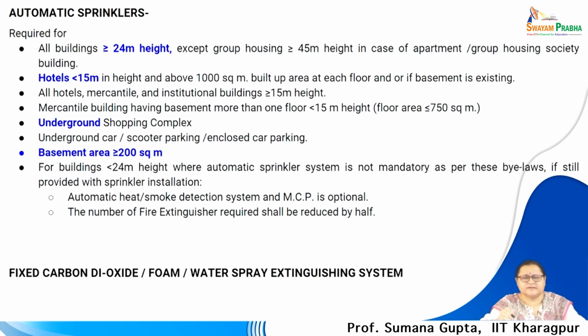Automatic sprinklers, as I had discussed: all buildings of more than 24 meters, which come under high rise buildings, will have automatic systems, and the basement area should be separated out. They should have their own automatic fire sprinkler systems where it is more than 200 meters square. We had earlier talked that for the upper parts 750 meters square is the mandate for automatic sprinklers. However, for the basement it is only 200 meters square. Automatic heat and smoke detection system for multi-level car parking is optional. The number of fire extinguishers required shall be reduced by half if there is an automatic heat and smoke detection system.